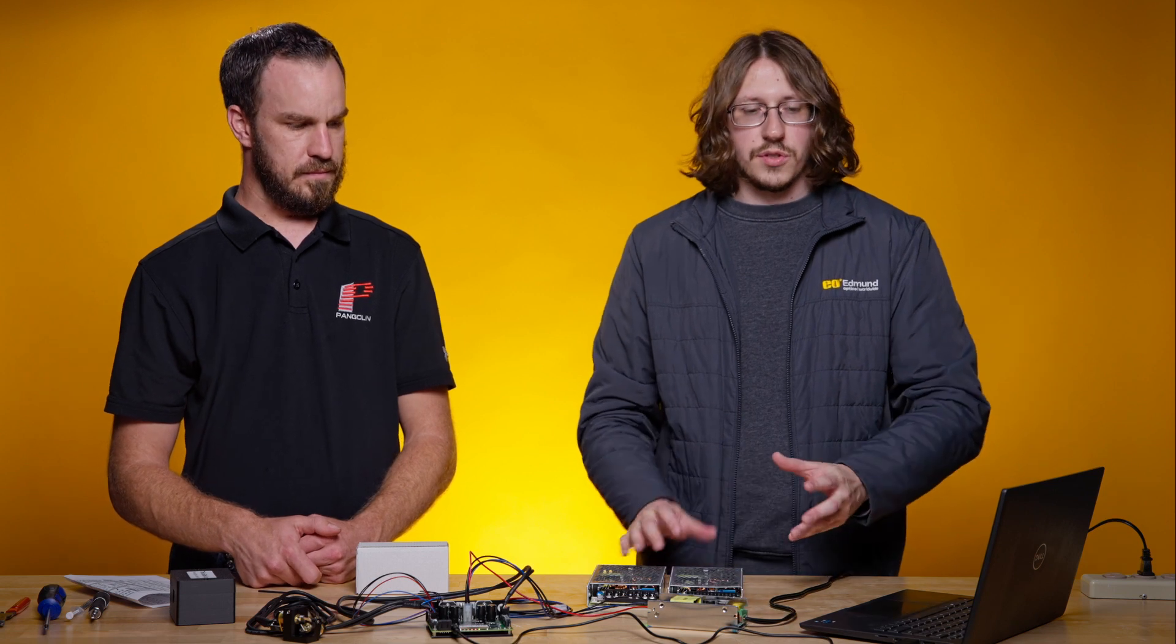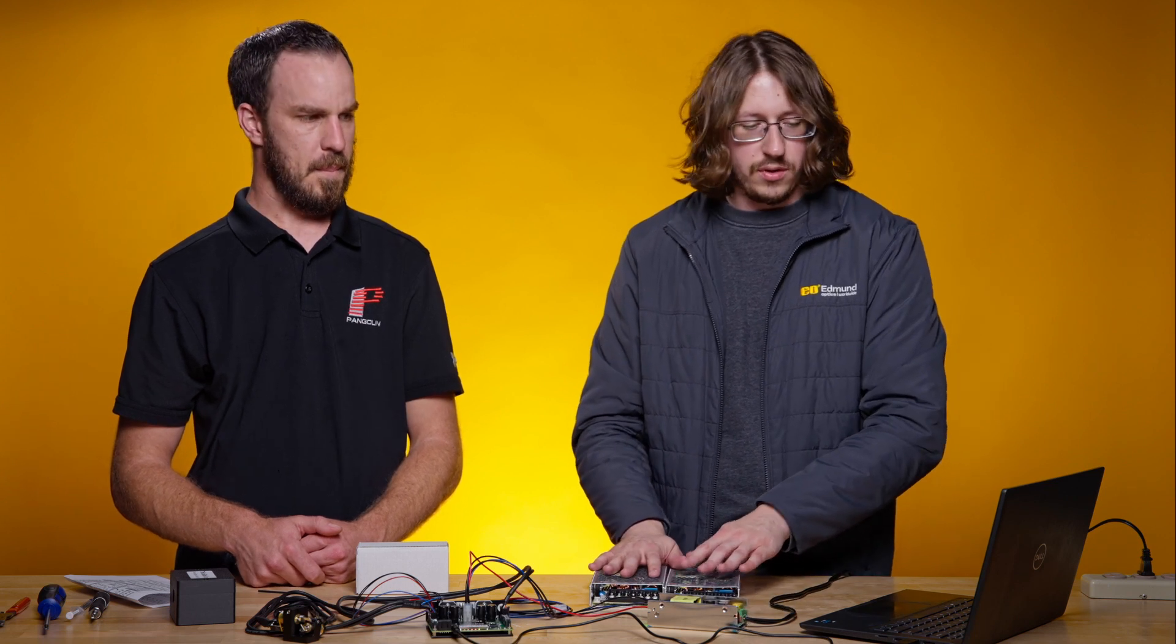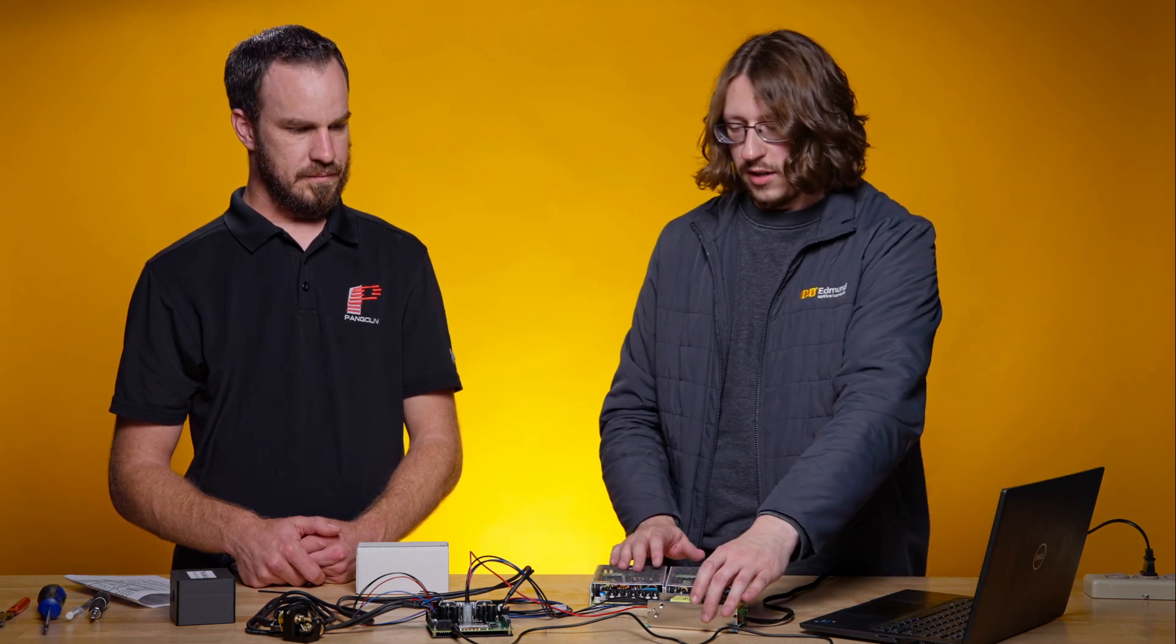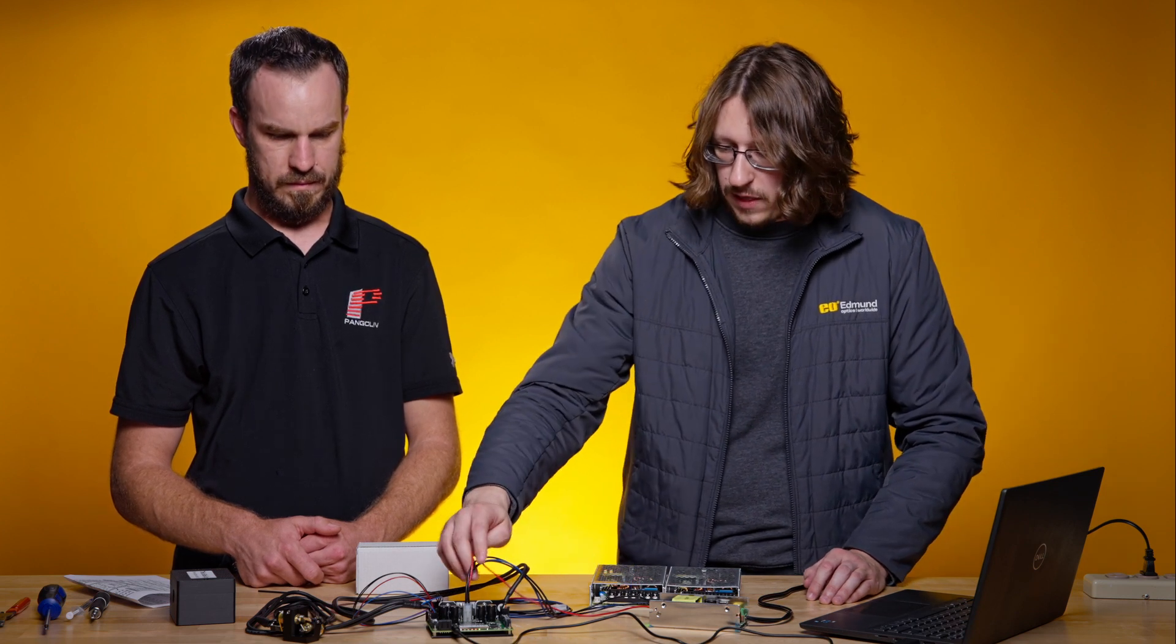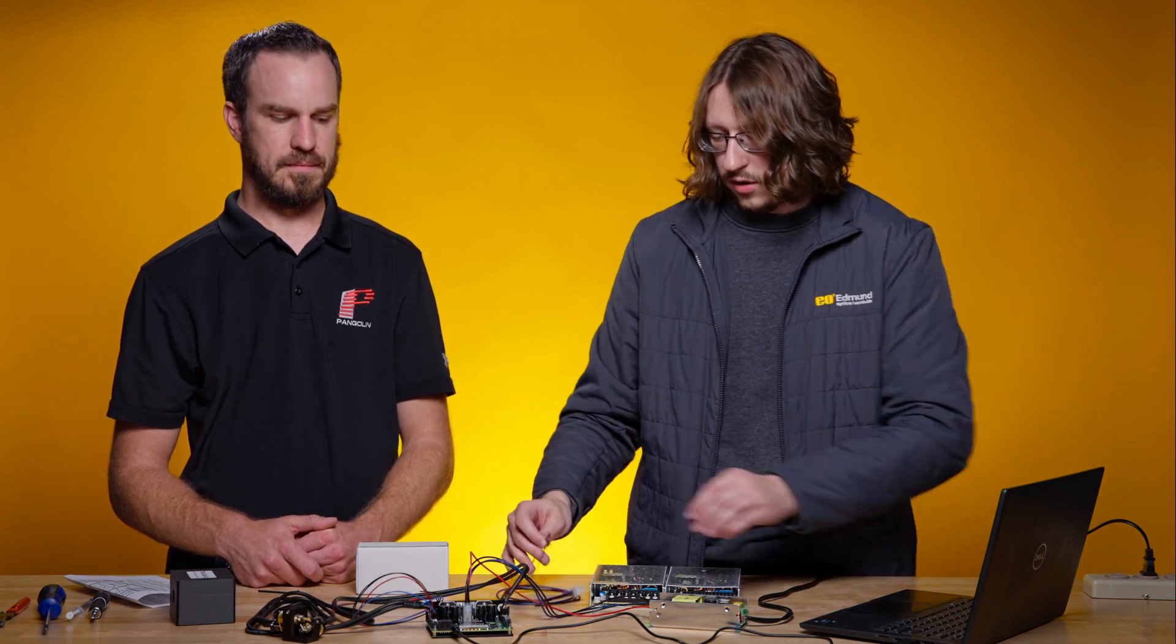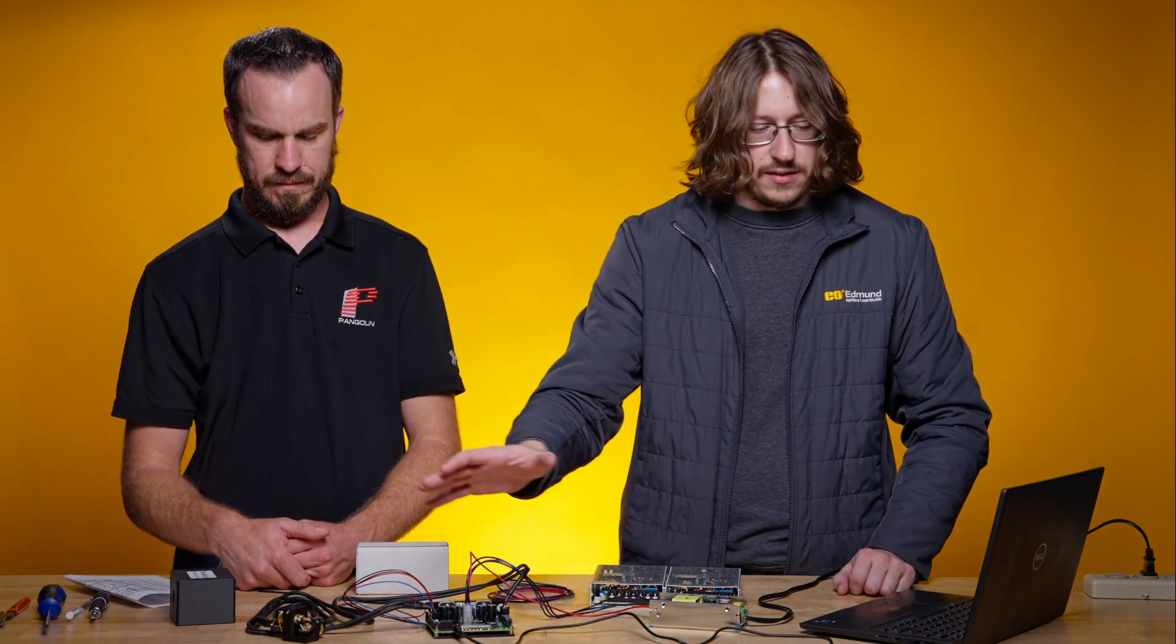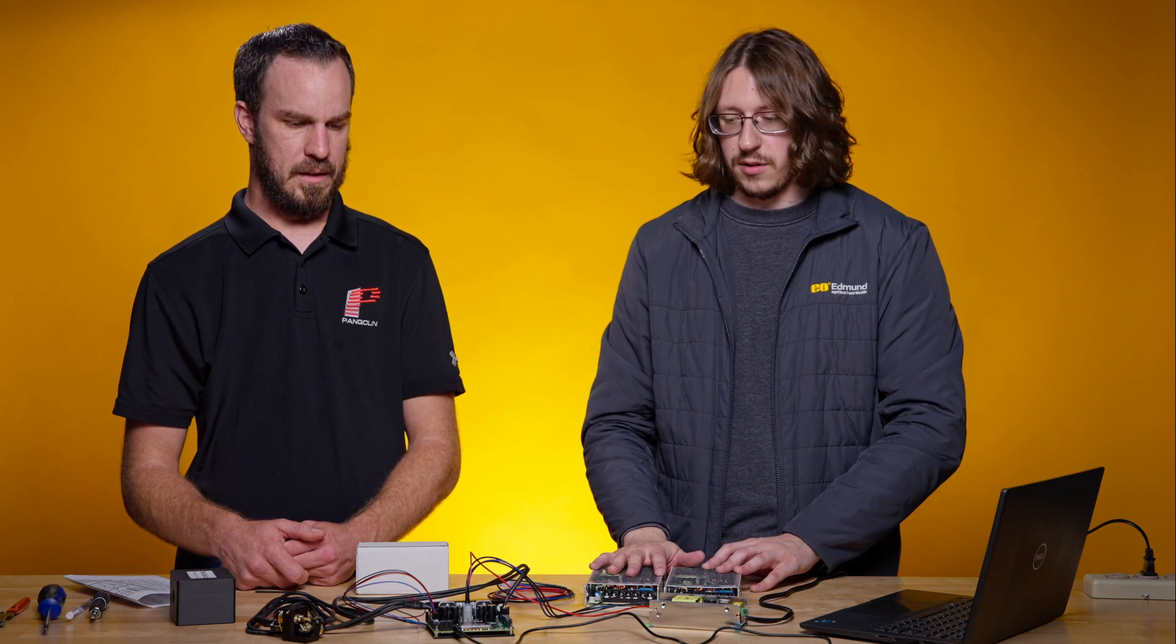So just to recap everything that we've connected, we've got the power supplies. So the US one or the European or rest of the world version, you need to provide your own power cable to the mains connection. The wire harness from the power supply to the Mach DSP is included. And then once you've got this all wired up, connect your galvo using the servo to galvo connection cables. If you want analog connection, that is also provided right there, already wired in here. And then lastly, you have your USB to Mach DSP connection cable, which you'll control through the software if you're not using an analog connection.